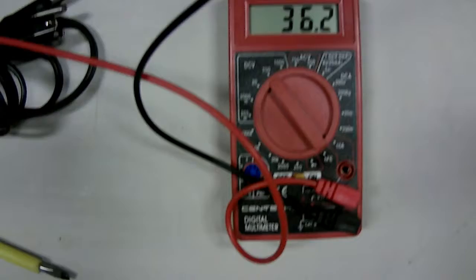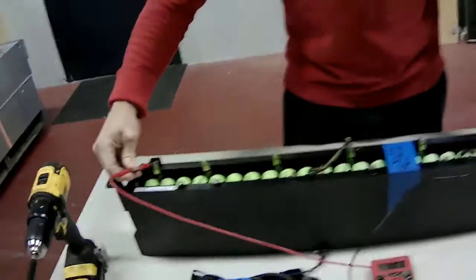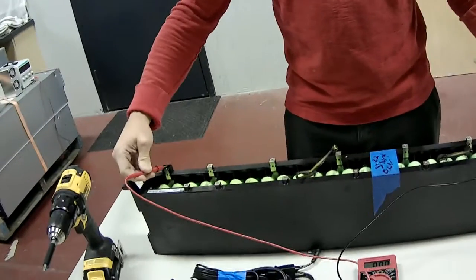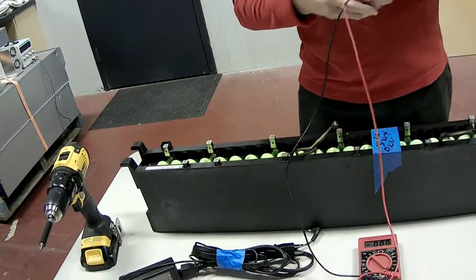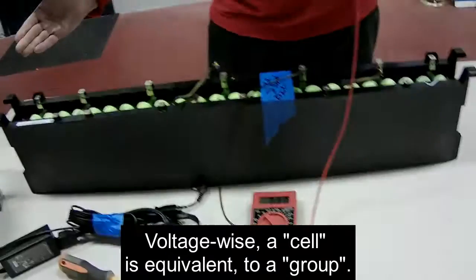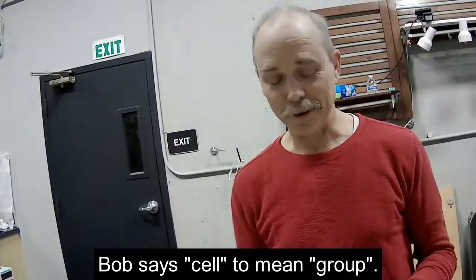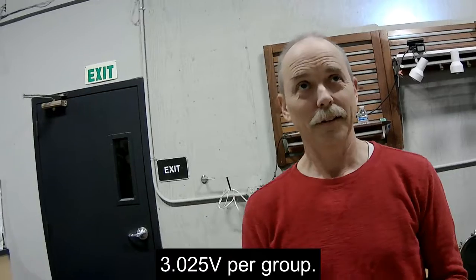36.3 plus 36.3. Okay, now that's a quick estimate of the health of the whole pack. From that, we could figure out that each cell is, if all the cells were the same, there's 12 in series, and we got 36.3 volts. 36.3 divided by 12 is 3.025. And 3.25 is not bad. It's not bad, not bad. It's a little on the low side.